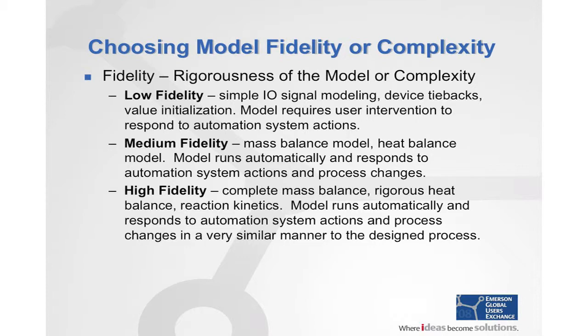Medium fidelity is generally what most people are going to need for operator training and testing. It's going to give you mass balance and heat balance models. The difference between that and high fidelity is the amount of tuning, the amount of additional data correlations, and the way the streams within the process are modeled. With medium fidelity models, you take all the streams with just a single component that does not change phase or state.